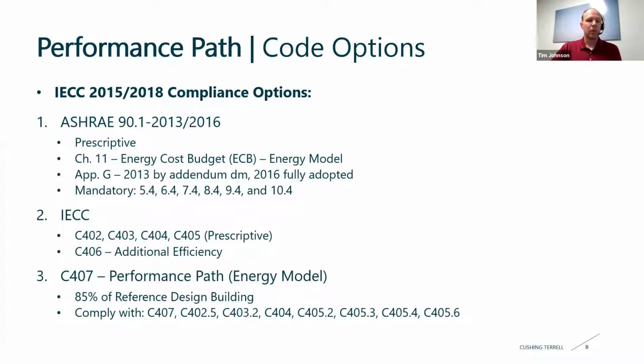If you do want to go performance path in IECC, we look to section 407, and that also has its mandatory requirements, and it also requires that our performance of our proposed design is 85% of the design building energy. So we have to save essentially 15% energy compared to a minimally code compliant building.